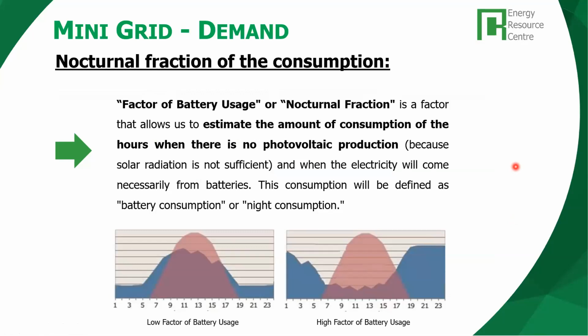It is important always in an off-grid system to be looking at the nocturnal fraction of the consumption, meaning how much of the energy that will be used will happen during nighttime. Okay. This is very important, obviously, because this is what we need to size the batteries. In this example, we have a low factor of battery usage. Again, this would be the case of a village with a lot of customers, with a lot of businesses, where most of the consumption, the blue area, will happen during the day. This is when the solar panels are generating electricity the most. So this is a high level of solar matching, low level of night consumption, and small batteries are required here. Perhaps not even batteries are needed here.